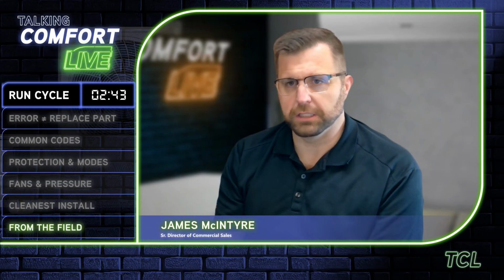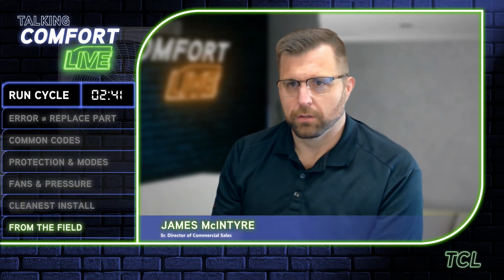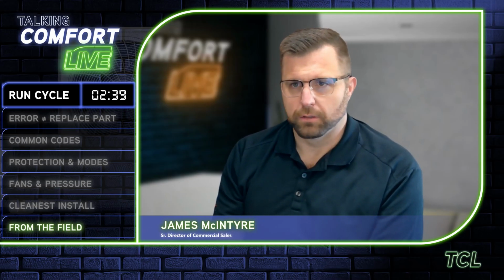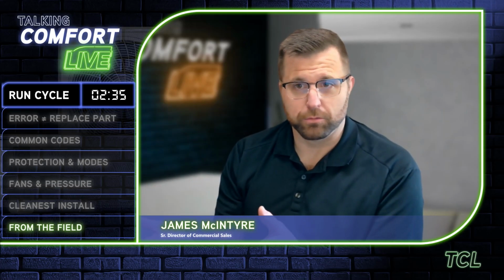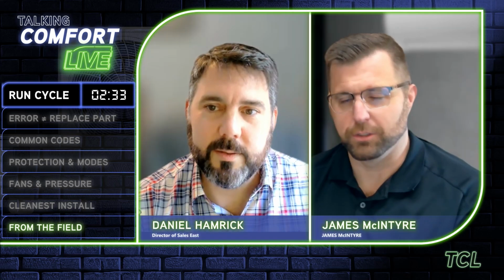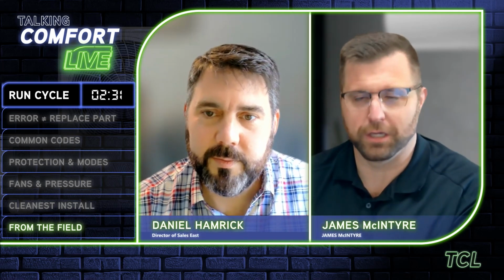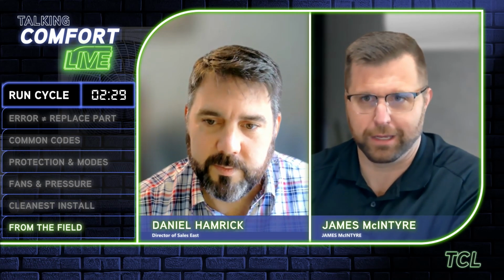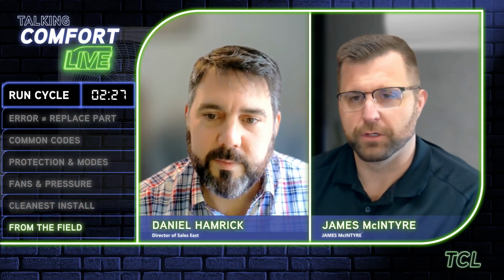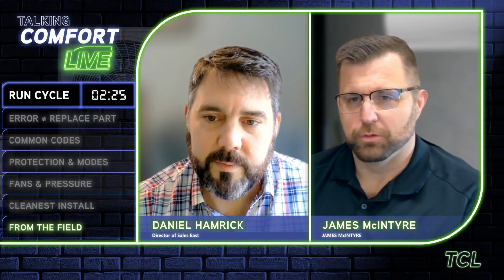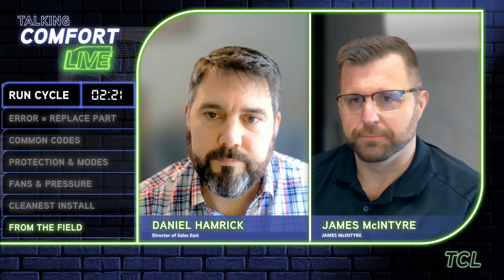And they had heat loss through the floor, like it was a single story, like it was out by itself or whatever. Not heat gain from the floor, mind you, heat loss. In reality, it was heat gain. They had plenty of heat gain coming from the first story that had its own heating system. So then you oversize the system in that case, right?